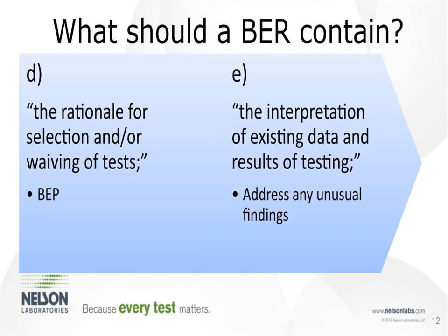And I'll tell you one situation that we had recently that was interesting. In a review of a sensitization report, I went straight to the conclusion, and it was noted in there by the laboratory that the device was considered a non-sensitizer. So I went ahead and thought, okay, I'm going to review the rest of the data here. And when I looked up in the report, actually 2 animals died during the course of the testing.